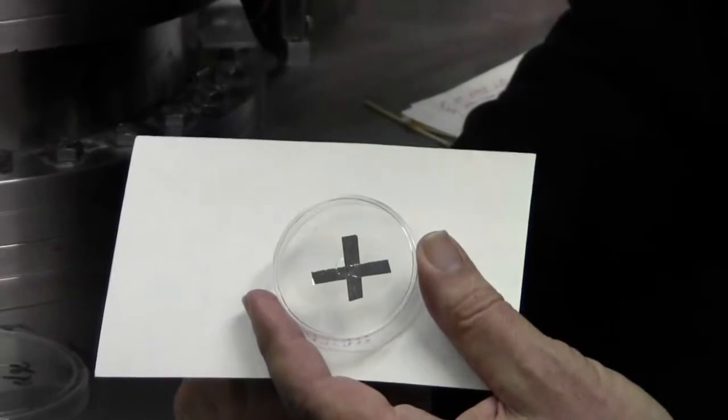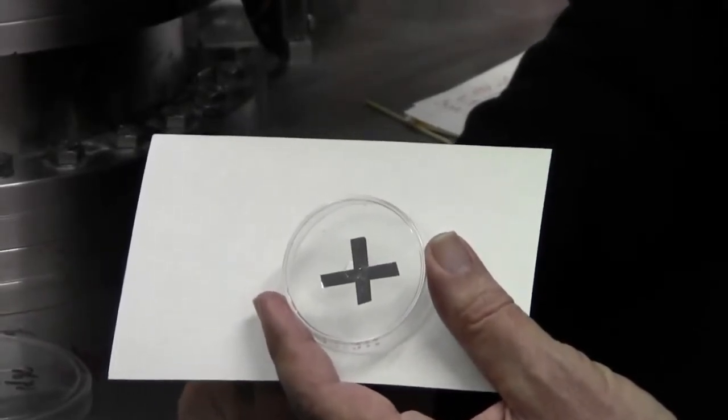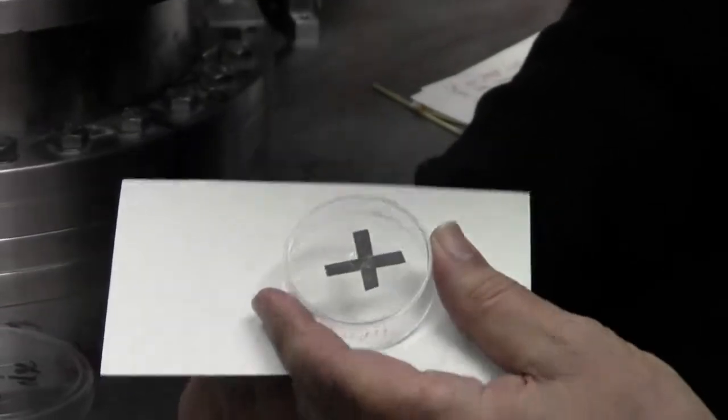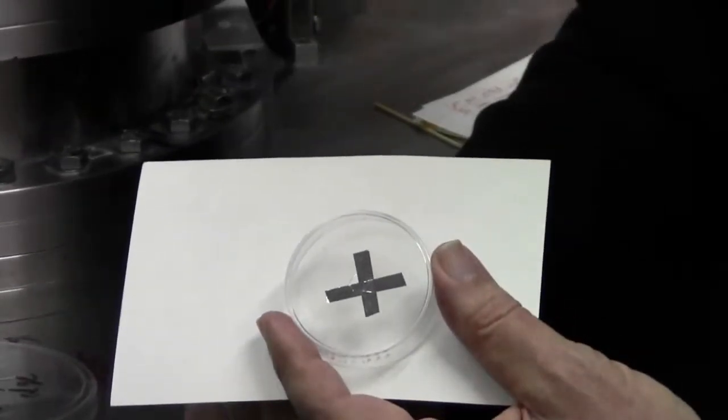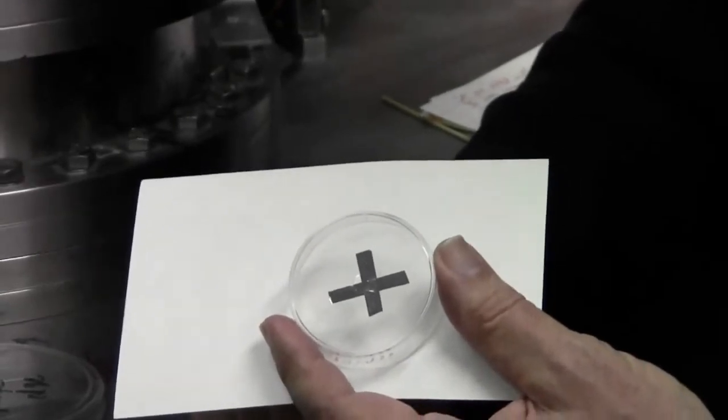Now we're going to be doing a knife edge scan and that is the way we determine the size and approximate position of our beam. What we have is two thin metal foils at right angles to each other and this is positioned over the beam exit.